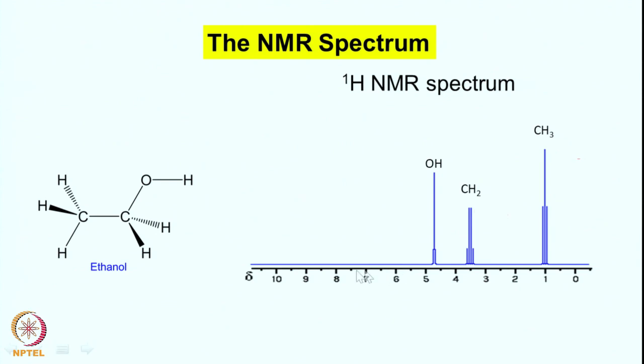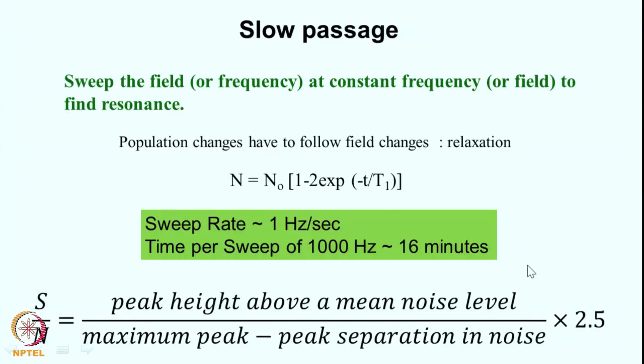In the early days, the method was called the slow passage experiment — you have a particular magnetic field, you sweep the frequency, reach the resonance condition and get the signal. Alternatively, you can keep the frequency constant and sweep the field. It was more convenient to sweep the field rather than the frequency in those days because the magnets were electromagnets and you can simply change the current to change the field.